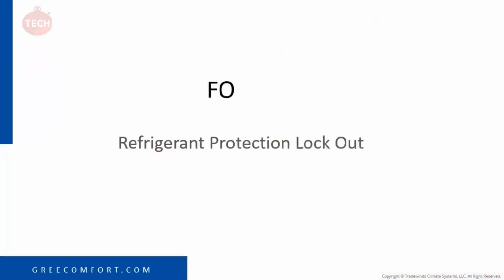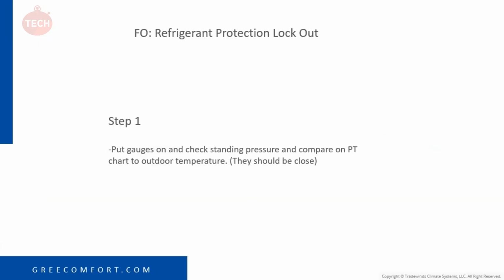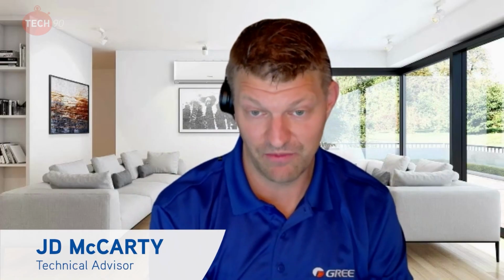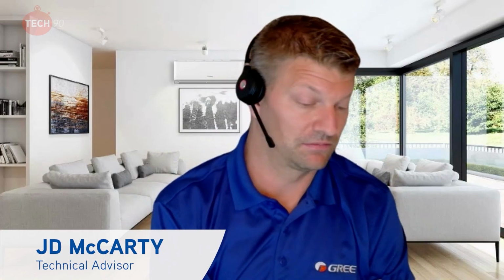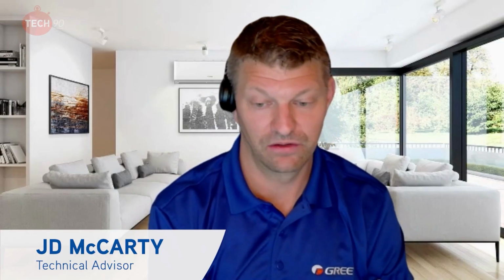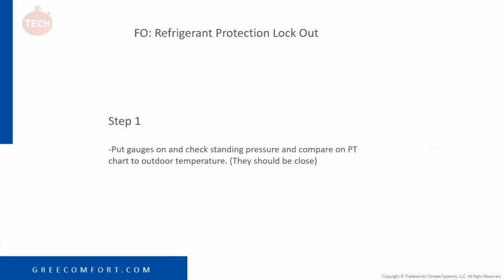So now we're going to get into our second code, which is FO. FO is refrigerant protection lockout. What I tell people, this is probably my most common call. If you're getting an FO code, it's a hard reset code. Before you do the hard reset and turn it back on, you want to make sure, obviously, we have refrigerant in there, because that'd be bad, to start the unit up without refrigerant.